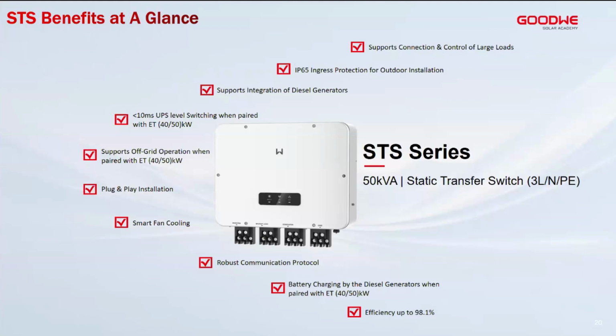In terms of charging, when you're connecting the STS to the ET50 or 40, you can set it up so that the diesel generator can charge your batteries on an emergency basis. So it's quite flexible: not only the grid, but you can also use the diesel generator. And in case your design is optimum, then the PV system should be able to charge your batteries themselves.